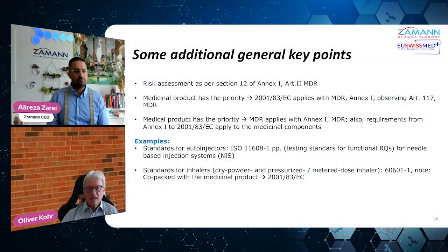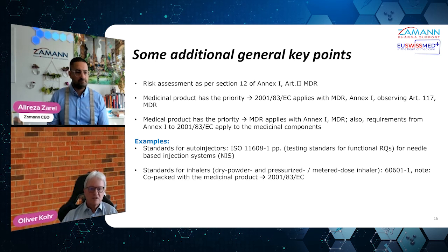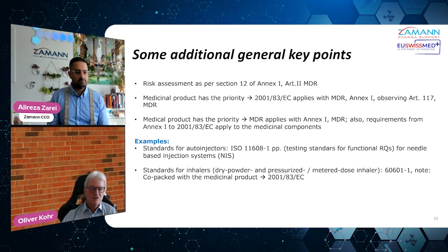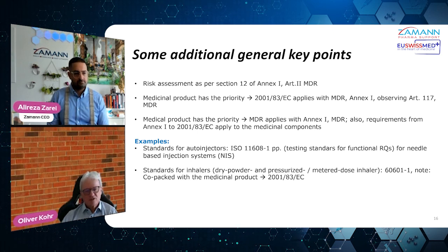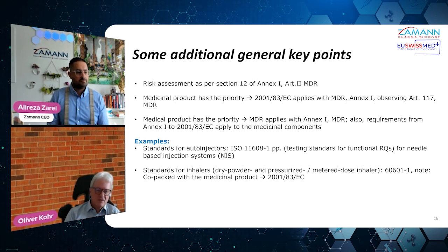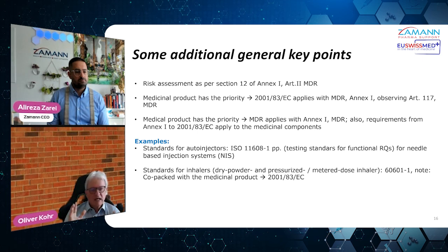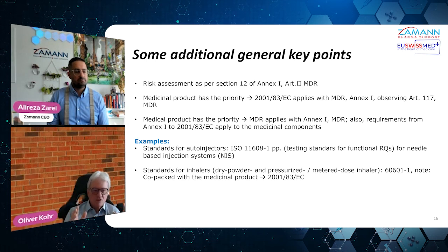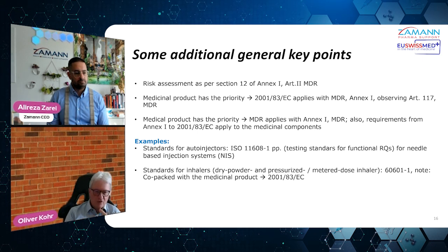Okay, now some final points. Very important, but what the notified body, in my experience, looks very, very closely at is the risk assessment. Why? Because of the new ISO 14971, 2019 and amended in 2022, if I'm right, they look very closely. Did you do a risk management plan? Do you follow the process as detailed?